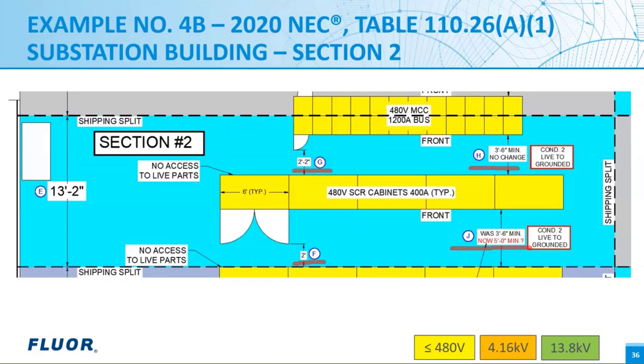But this is one of those areas where we're going to err on the conservative side, like most engineers do, and consider the intent of this new rule change. And we're going to leave 2 foot of clearance between the open door edge when it's at 90 degrees to the equipment and the back of the next row of cabinets shown near bubble F. This makes the minimum dimension near bubble J 5 feet instead of 3 foot 6 inches. So we've added 18 inches here.